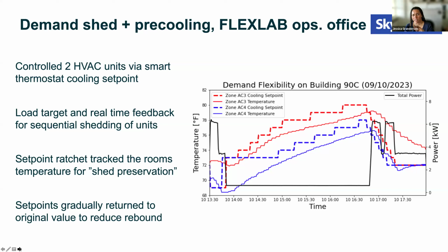The dashed lines are the set points for those units. In the beginning, they're low at that 1330 for the pre-cool. Then they ratchet upward through the duration of the shed. The solid red and blue lines are the actual temperatures for the zones, and the black is the total load. So you can see that just after that 1330 time period, we drop load on one unit, and then the next unit, and that will persist as we ratchet the temperature set points up. And then we return to basically our pre-event load levels, and we do that without a huge spike at the end of the period.